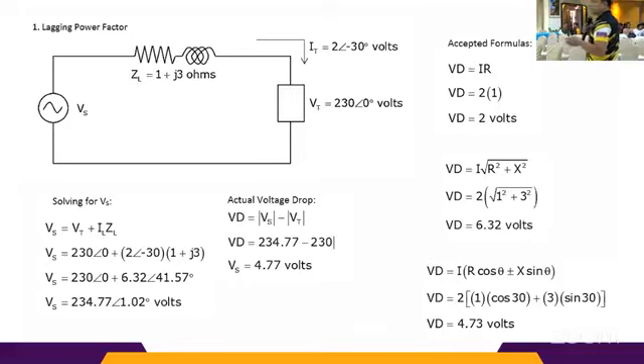Okay? Then we also have the accepted formula, VD is equal to I times R. So 2 times 1, the resistance, VD is 2 volts. This is another formula, I times the impedance, so the voltage drop is equal to 6.32. Then we have another formula here: voltage drop is equal to I times R cosine theta plus or minus X sine theta. Since this is a lagging power factor, for the plus or minus we have to use the plus sign.